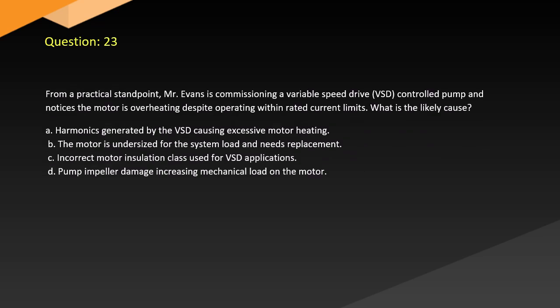Question 23. From a practical standpoint, Mr. Evans is commissioning a variable speed drive (VSD) controlled pump and notices the motor is overheating despite operating within rated current limits. What is the likely cause? A. Harmonics generated by the VSD causing excessive motor heating. B. The motor is undersized for the system load and needs replacement. C. Incorrect motor insulation class used for VSD applications. D. Pump impeller damage increasing mechanical load on the motor.